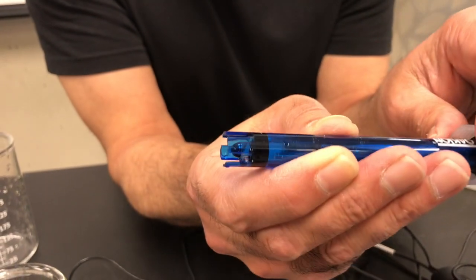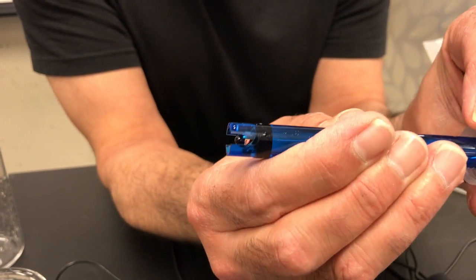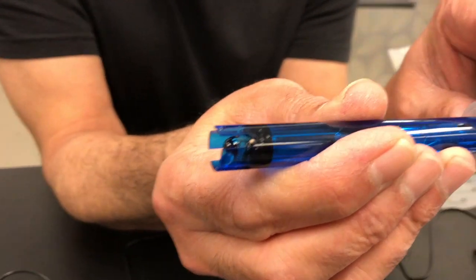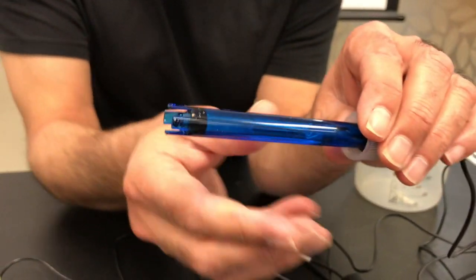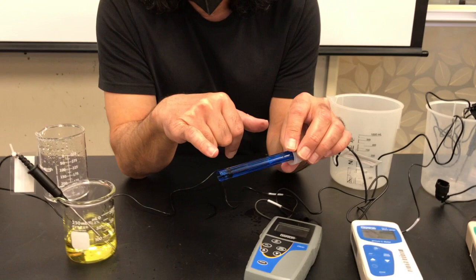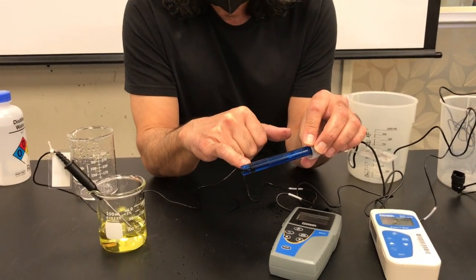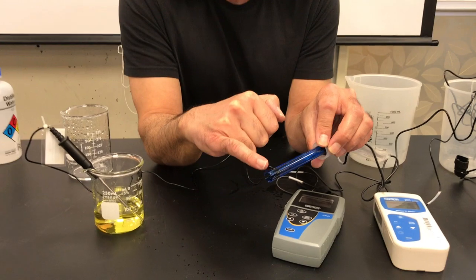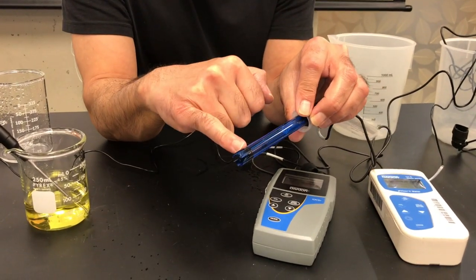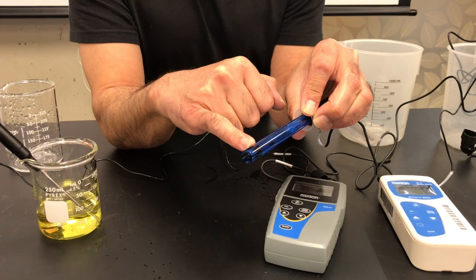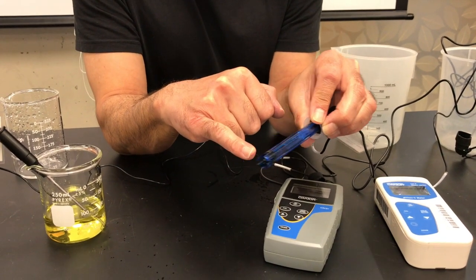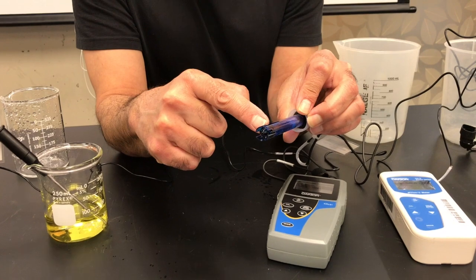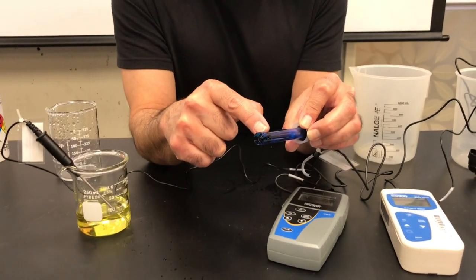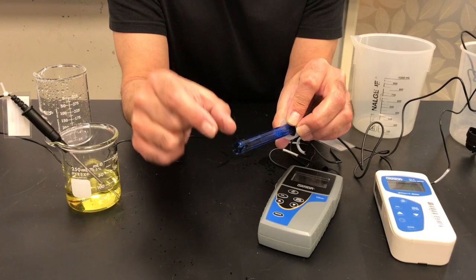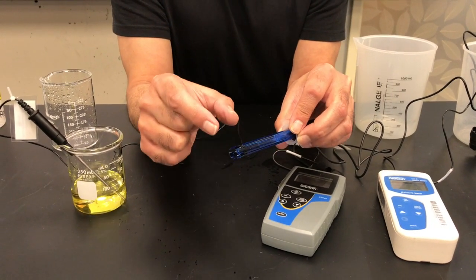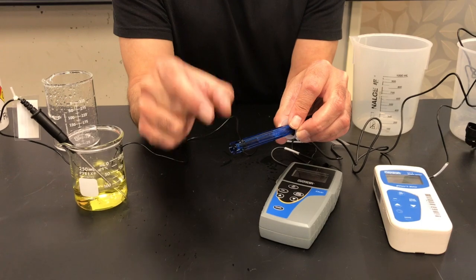It has two. There's one there, and right on the opposite side, there's another junction. The reason I want you to know about this is that in order to get a good measurement, not only does the membrane need to be completely submerged in your sample, but that junction also needs to be submerged. You don't need a lot of sample to get a good measurement, but I always want to make sure that a good portion of the tip of the meter is submerged in the sample that you're measuring. Okay.